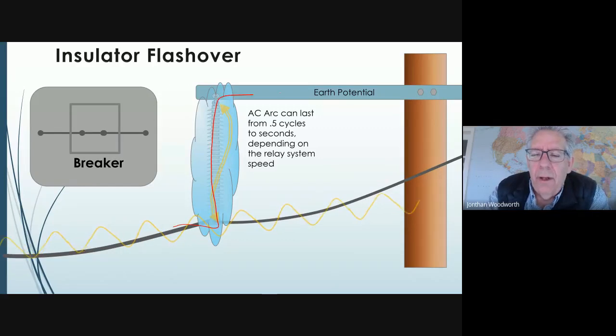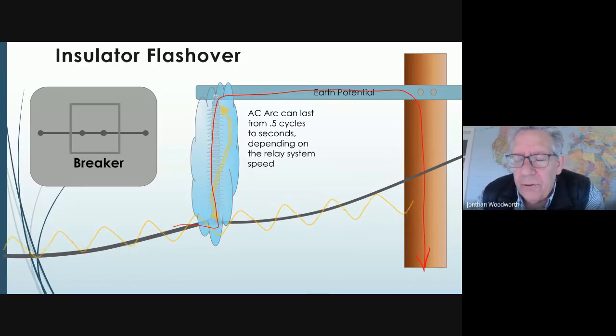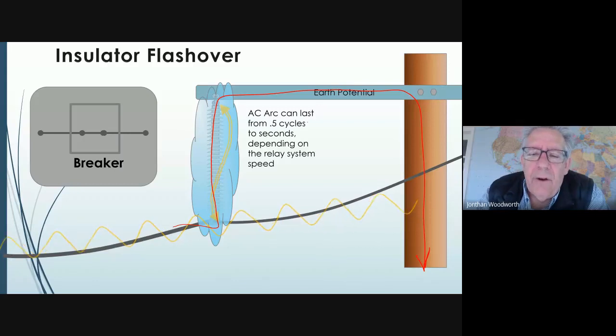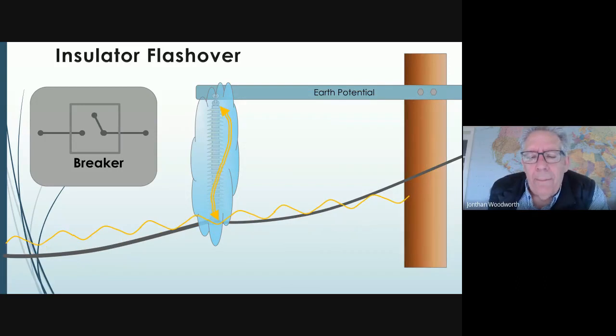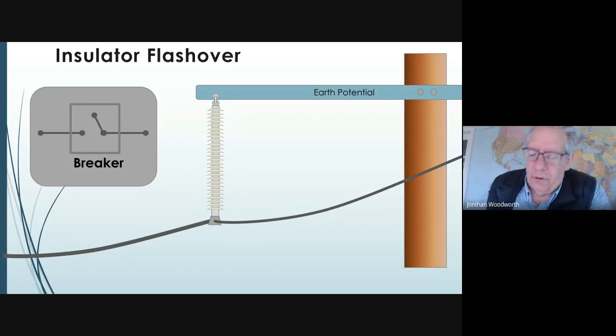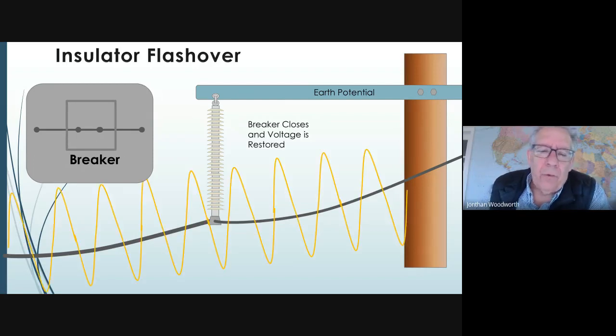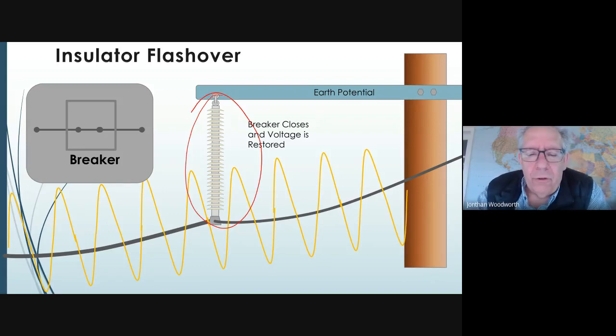So at some point, the power system senses a fault. The current is flowing over and down to earth, so it senses this ground fault, and very, very fast systems can sense it in, say, half a cycle. Most of the time it takes multiple cycles to sense it, and then the breaker opens up, and when it opens, it gets rid of the arc. There's no more voltage on the system for a moment, maybe 4 or 5 or 10 cycles. Now the voltage comes back, and when it comes back, there's no short circuit anymore. So that's the whole sequence of what happens when lightning strikes a line.